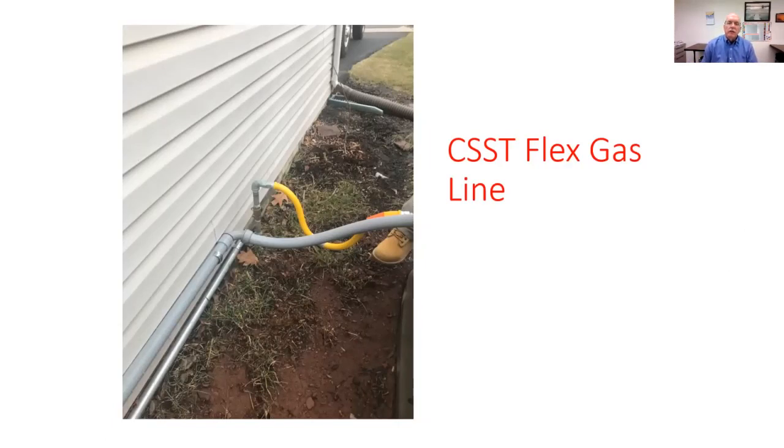And this system here, I have at the present time 10 grandkids, and I can tell you that if we had all 10 grandkids over at Easter or something like that, and they're running around the yard looking for hidden Easter eggs, I can tell you right now that this electric line and this gas line do not stand a chance. They will not survive these kids running around. They will jump on them. They'll use them as swings. They'll trip over them and all that. So we cannot do an installation like this.